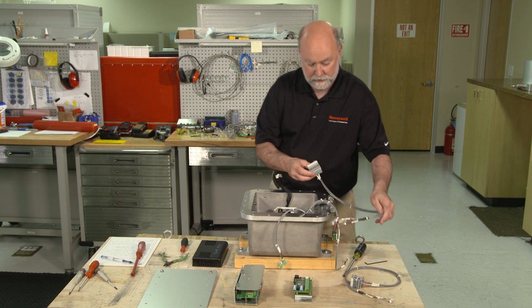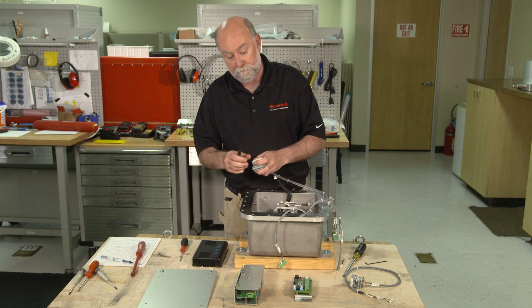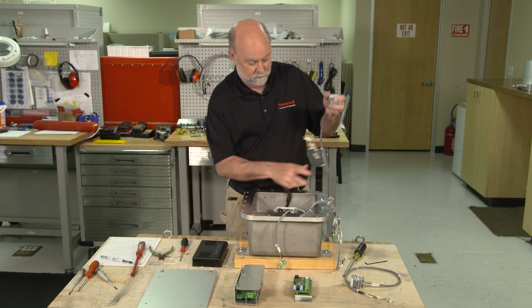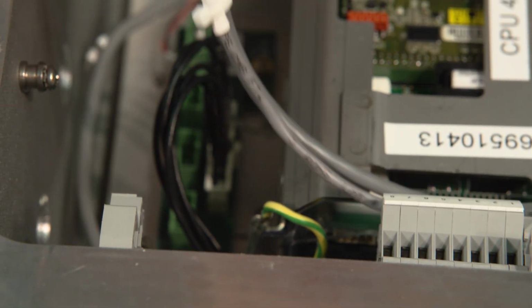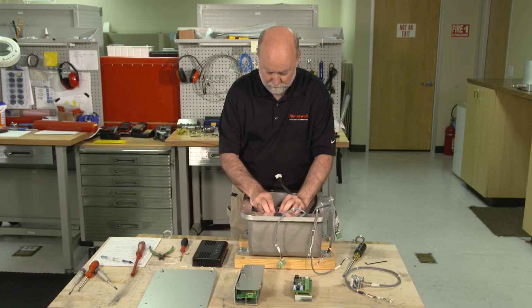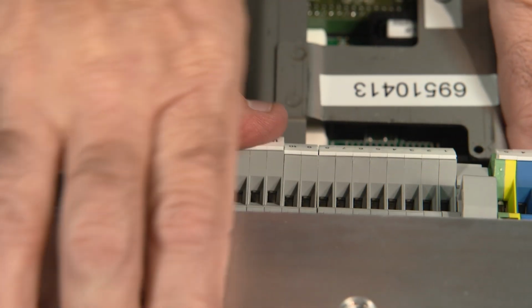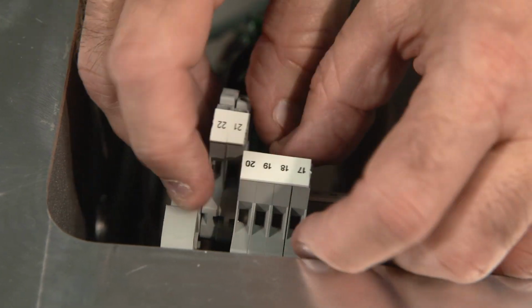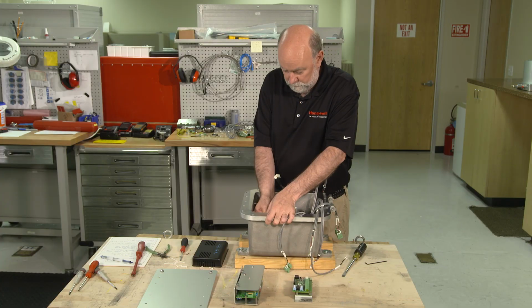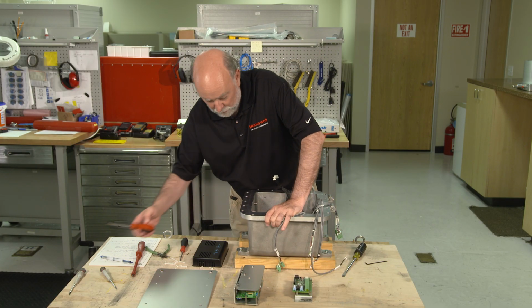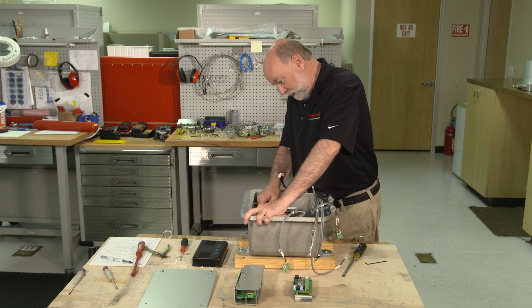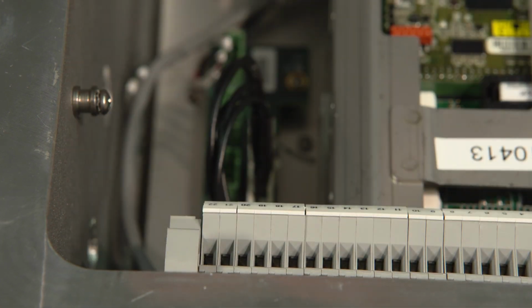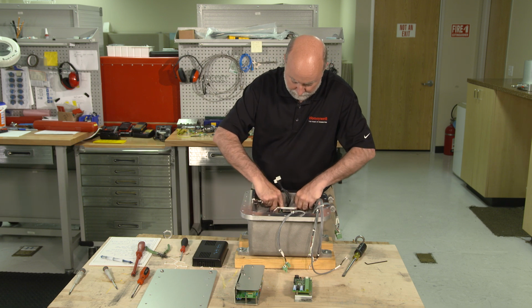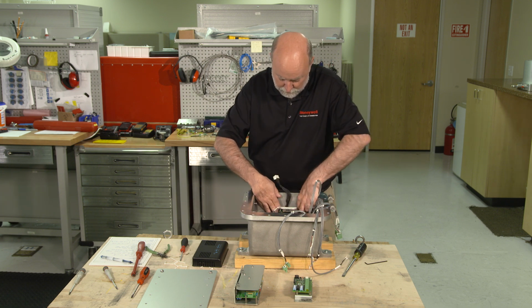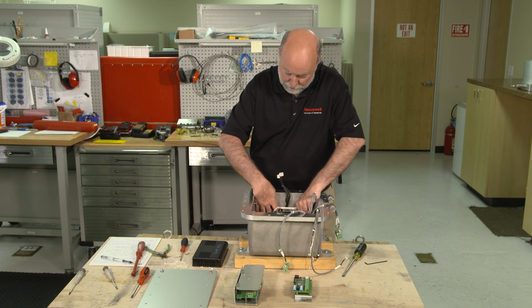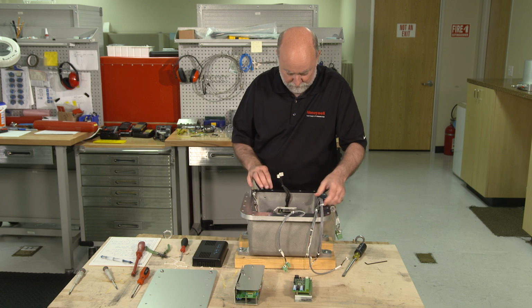Next section is the 9 through 16 TB2 blocks. Same procedure. We're going to get the wires down through the gap there. Snap those in place, and finally, it's the 17 through 22. Snap those in place. I can slide my right-hand separator block over till it's snug against the number 22 block. Just tighten that down. At this point, I'm tucking some wires underneath the connector of the wiring harness that goes from the backplane board over to the field terminal board.